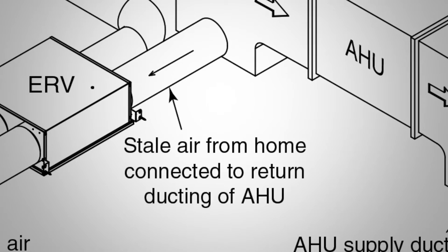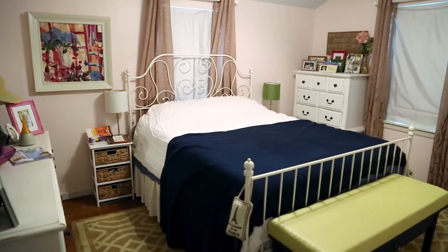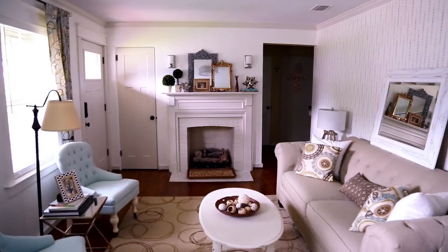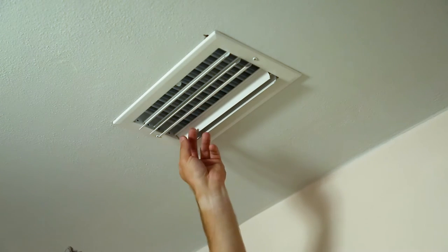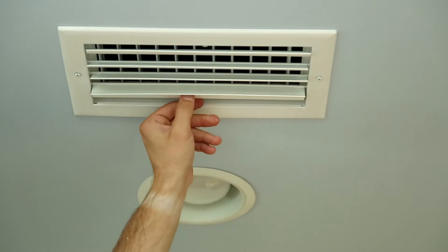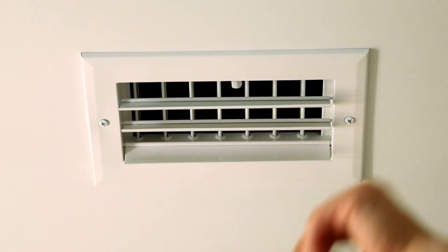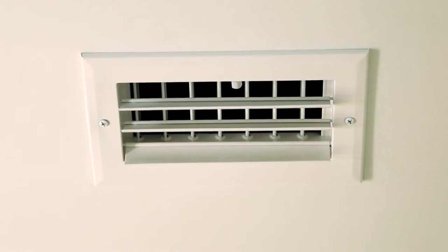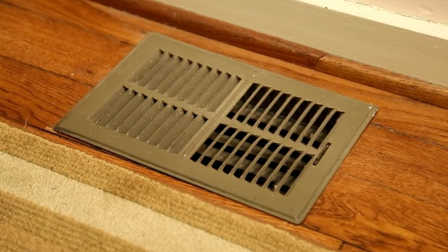If you are using the second AHU configuration, you'll want to install fresh air distribution registers in bedrooms, dining rooms, living rooms, or the basement. Fresh air distribution registers should be located as far as possible from the ERV stale air registers. Install fresh air registers in the ceiling or on an interior wall 6 to 12 inches below the ceiling. If you must install the fresh air register in the floor, direct the airflow up the wall.